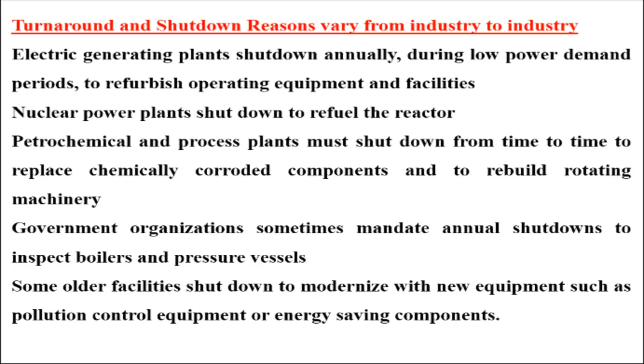Let us ask one question now. Is there any job planned for turnaround shutdown that could be done under normal conditions, or on day-to-day maintenance? The answer is yes or no. Of course, the best answer should be no, because as we mentioned, this period of time is expensive. We are under pressure. We are forced to do a lot of maintenance in a short period, at high expense, with high use of outsourcing and contractors, with many people involved. So it's not a pleasant period to do maintenance unless this maintenance is a must and it cannot be done during the normal or running maintenance. However, of course, the answer should be no. No maintenance which can be done during running maintenance should be done during shutdown maintenance unless there is a justification.